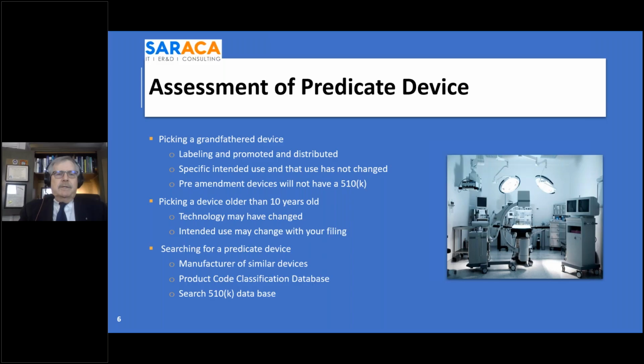The problem with getting any information from a grandfathered device is you don't know specifically what the labeling was approved for, what it was promoted for, and where or what it was distributed for. This makes a huge difference in what you can do with the device. So there is no 510K for pre-amendment devices. You'll have to get your information from labeling that's out there in the market, taking snapshots of their website, taking snapshots of the device, or obtaining samples of their labeling and their directions for use. That's one of the few ways that you can get that. The problem with that is that you don't know what the device was tested to, if anything, and you don't have copies or any indication of which standard was used, if anything.